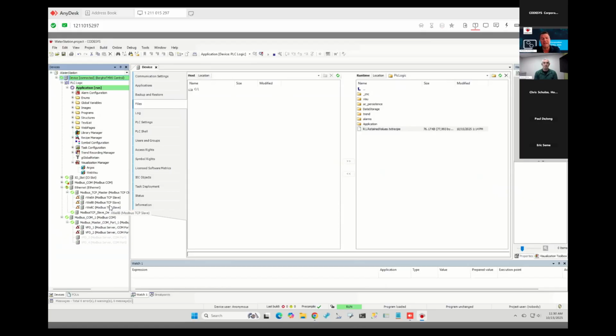So some of our updates will be direct interface to some of the alarming systems. So writing the API inside, or the gets and the puts inside of our program, so we don't have to go through email servers for our alarming, and using the Modbus function block. Most of the water wastewater is going to be Modbus protocol, either RTU or TCP. But writing that and using that so that we do not have to rely on the product tree, which is what's limiting us right now on some of the things we're trying to do. Because we have to disable, enable this through the WebVisU at runtime, because we don't want to have to go in here and do a ton of work inside the actual program before we deploy on site. So that is our smart pump controller.